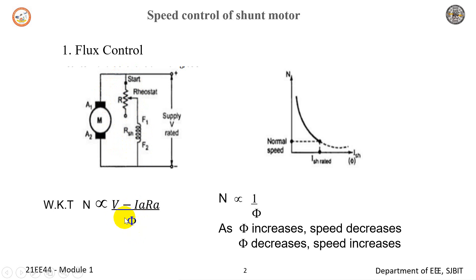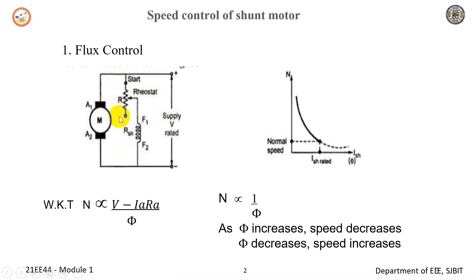Since the flux discussed here in the denominator is a field flux, if I vary this field flux — as n is inversely proportional to phi — if I increase phi speed should decrease and if I decrease phi speed should increase. To obtain this change in flux we need to change the current in the field winding. For a shunt motor, as long as the supply is constant, the current in the shunt field is also constant. Thereby, to vary the shunt current I need to insert an external resistance R to vary it.